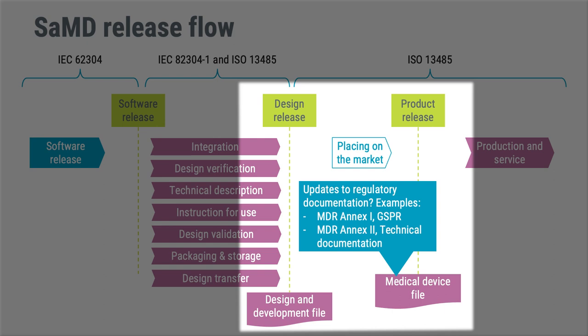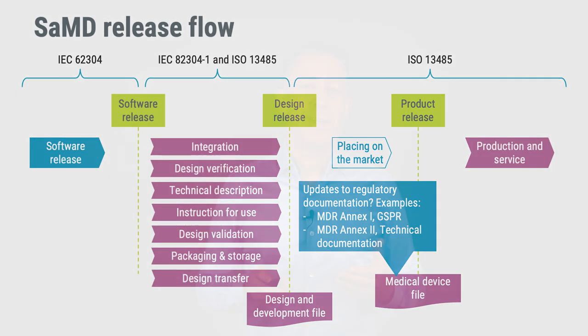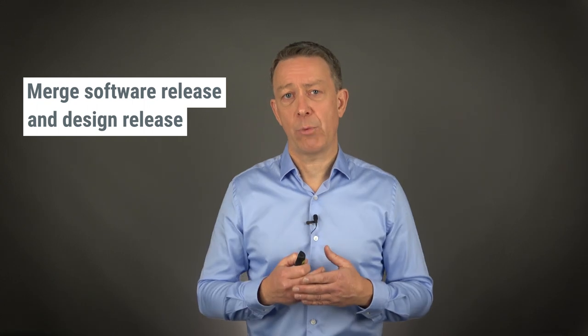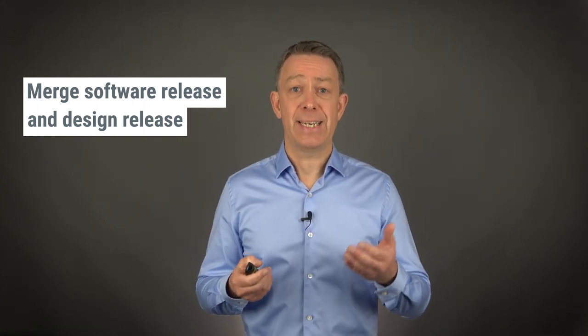Please ensure you maintain relevant regulatory documentation — for example, keep the MDR general safety and performance checklist and technical documentation up to date. When working with standalone software, you can merge software release and design release into a single activity — for example, by including technical documentation and instruction for use as configuration items in your development work. This is a lean approach and makes sense in most cases. Still, I want you to be careful about placing software on the market without considering all the activities and deliverables needed for a product release. Now you know the difference between a software release, design release, and a product release.